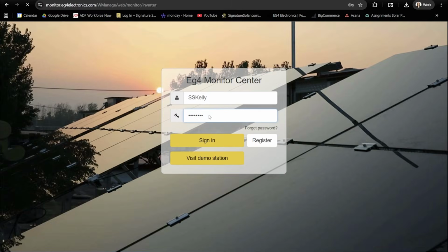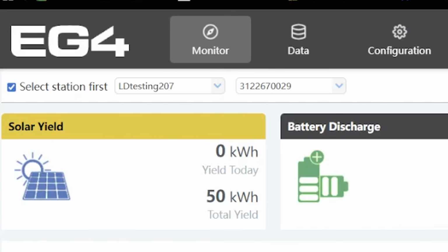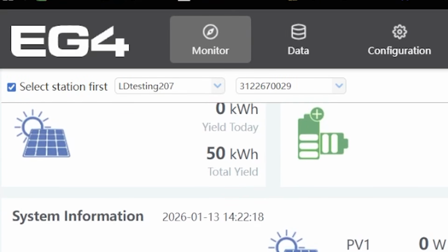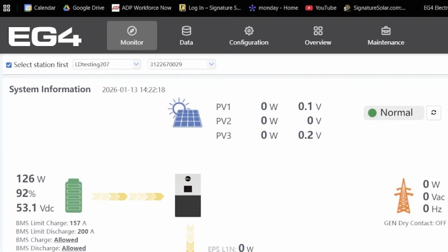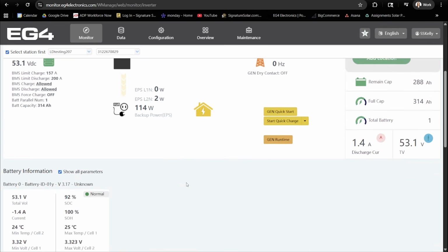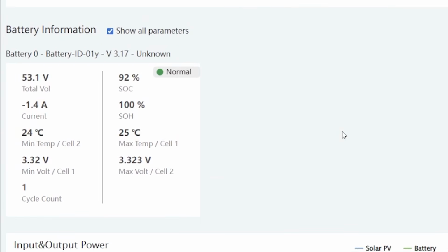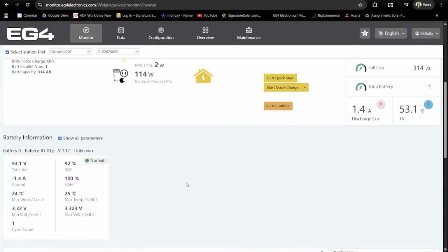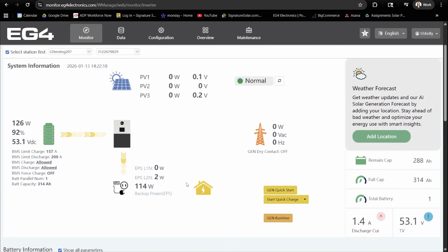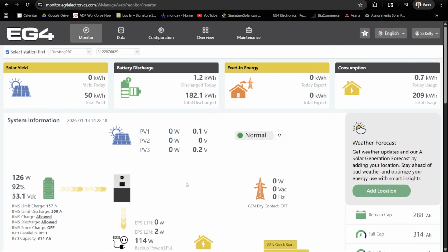Now we need to log into the EG4 Monitor Center. Start by confirming you are viewing the correct site and system by checking the station name and the inverter serial number. Once you're on the system operation page, confirm that you can see detailed battery data. Being able to view information like voltage, current, state of charge, and overall status confirms that communication between the inverter and the battery is working properly. If that detailed data is populating as expected, it's a good indication that the OTA update should go through successfully.